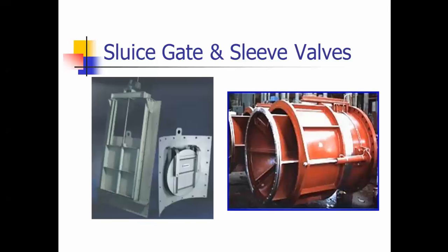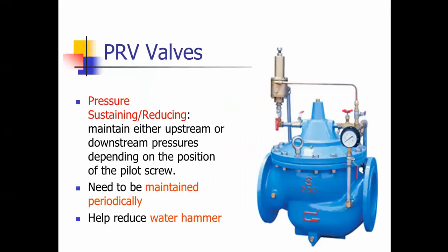And then the one on the right is a sleeve valve. And so there's sluice gates and your sleeve valves. Your pressure regulating valves, you have pressure sustaining and pressure reducing, and they maintain either upstream or downstream pressures depending on the position of the pilot adjustment. They should be maintained periodically. Annually during low flows is when the system I did, we went in and checked those in the wintertime during the lower flows. They also can help reduce water hammer.